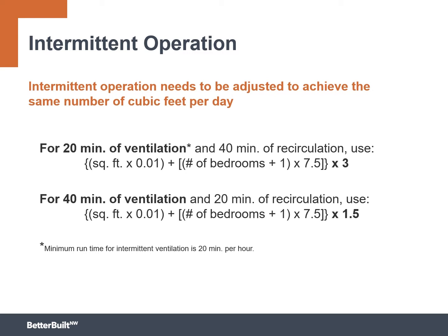So let's take a look here. Most of our HRVs are recommended to run 24/7. But if we're choosing not to do that, then we need to make these adjustments. It also may change what HRV we're able to select based off of these volume changes. So choose the unit that's based on medium speed to meet your airflow is ideal for continuous, but you may need to meet based on a medium high or high fan speed if you're going to do intermittent ventilation.